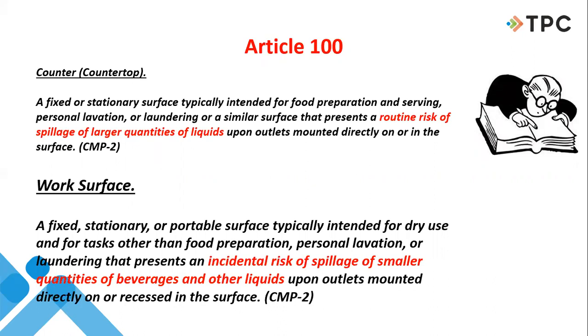The key difference here is where we have incidental risk of spillage of smaller quantities of beverage and other liquids. So a counter or a countertop is where we would routinely expect the risk and likelihood of spillage of large quantities of liquid. A work surface primarily would be expected to be a dry location, where every now and then someone may spill a cup of coffee or spill a soda or whatever. But it's not expected that, by the very nature of the location, quantities of spillage would be there and would take place. So they had to differentiate between these two locations in order for it to become more clear what type of location these different types of receptacles were intended to be installed in. So a lot of clarification, a lot of desire for better understanding, not just within the workers' world, but also within code enforcement as well.